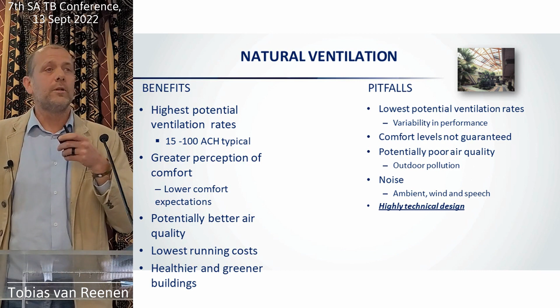However, when the system fails, when the windows are closed, if the wind's not blowing at all, you've got potentially the lowest ventilation rates because of the variability in performance. Your comfort levels are not guaranteed. You've also got potentially poor air quality if no air is moving. If you've got a lot of outdoor pollution, soot, traffic, even noise pollution, dust, they can get into your building. We've spoken about noise already. You've got to consider internal acoustic considerations like ambient noise and wind and speech transmission and so on in the space. So the design becomes very quickly quite technical and difficult to do. Not something that you should be attempting without a suitably qualified and competent engineer.